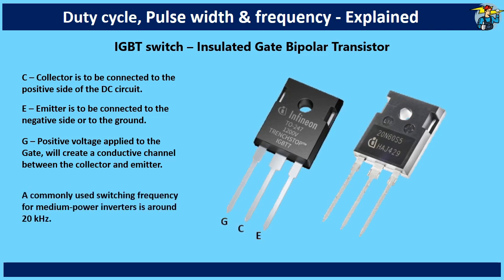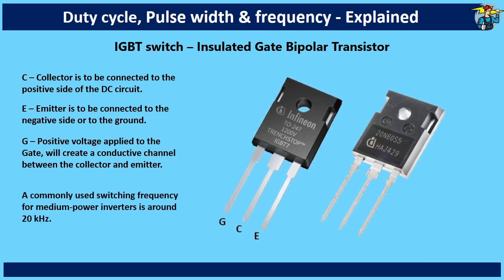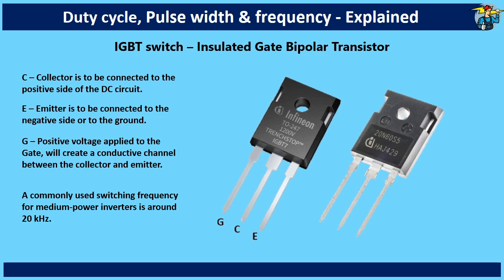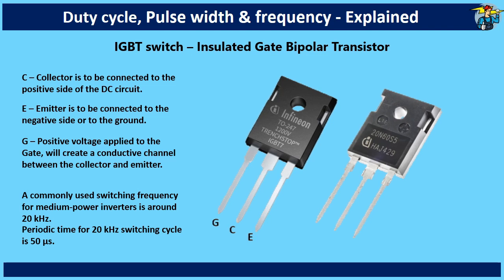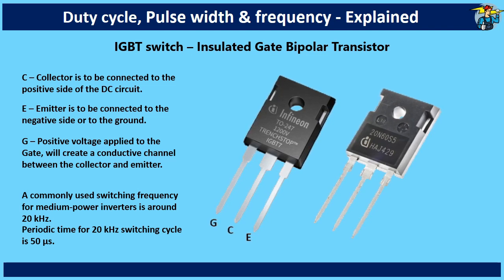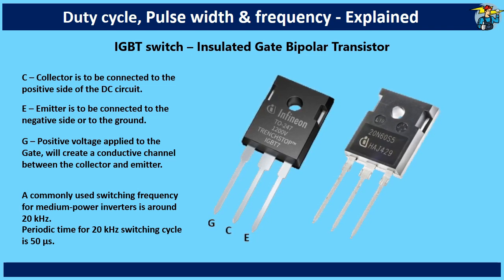A commonly used switching frequency for medium power inverters is 20 kilohertz. Periodic time for 20 kilohertz switching cycle is 50 microseconds, and is effectively achievable with these type of IGBT switches.